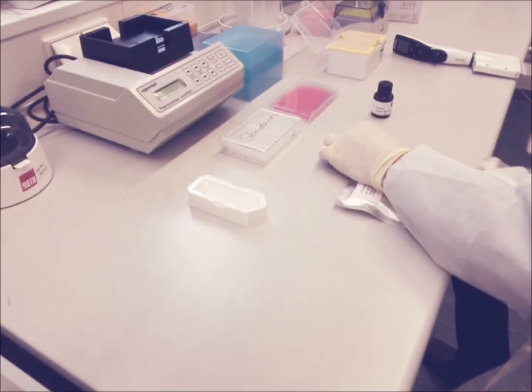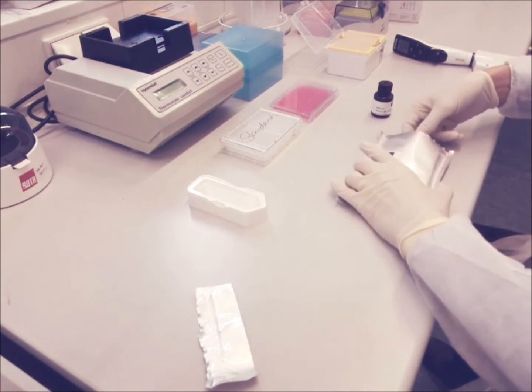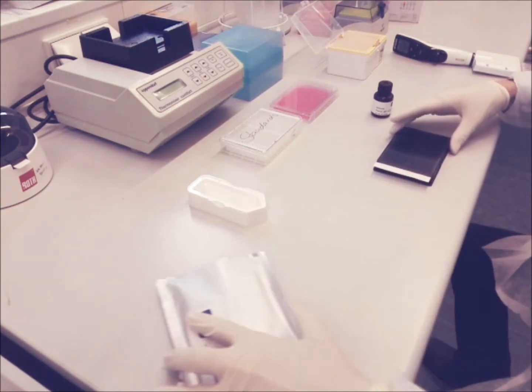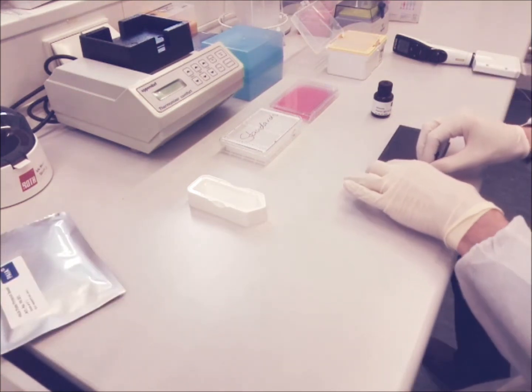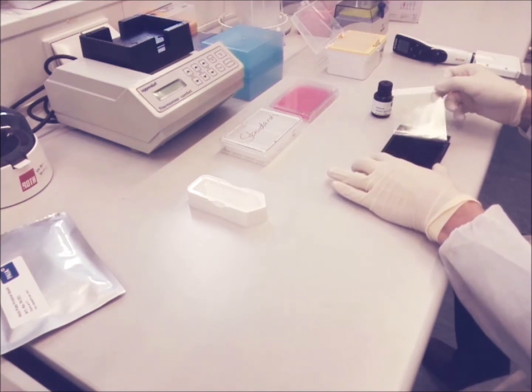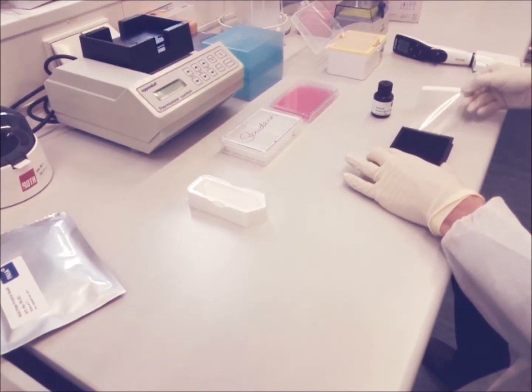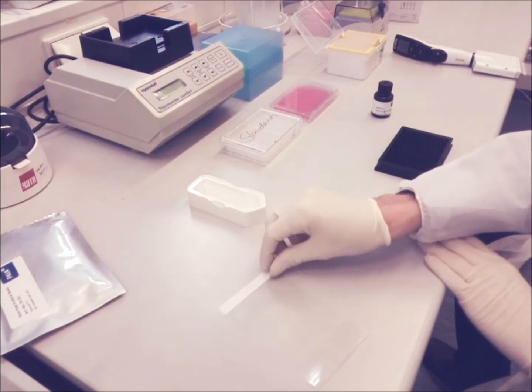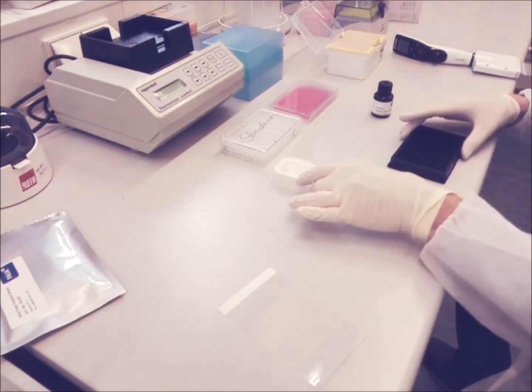Our assay kits contain the special PAIA microplate and a ready-to-use buffer with a fluorescence marker. In the first step of the assay, the buffer is dispensed onto the dried-in beads in the microplate. Typically around 50 microliters of buffer is added into each of the wells.